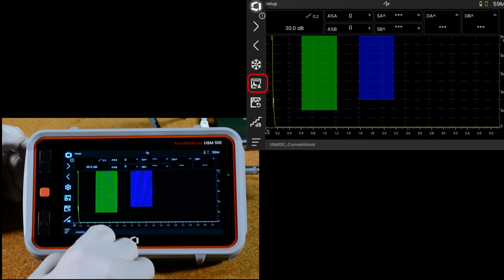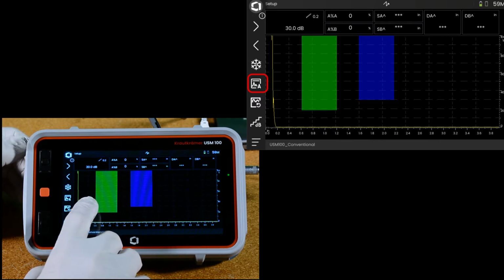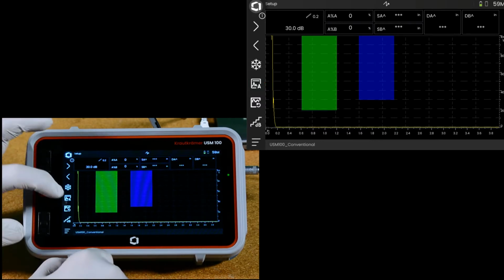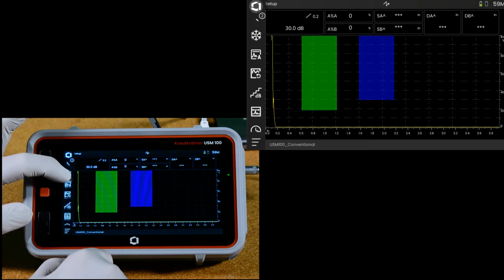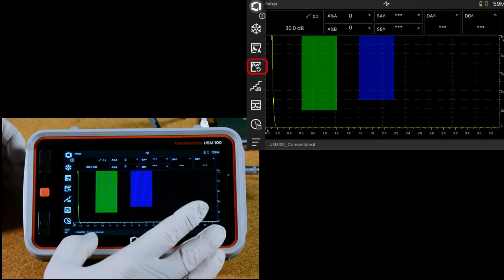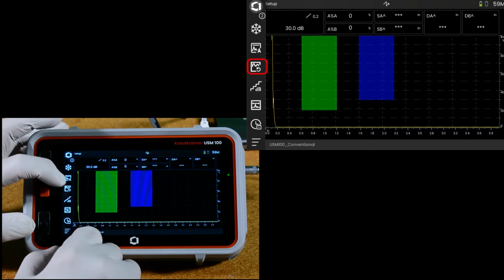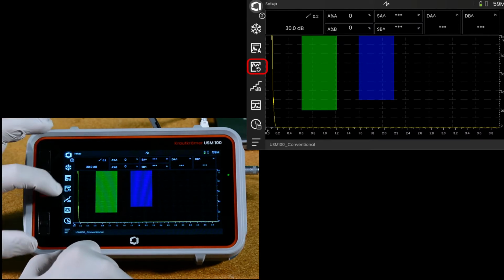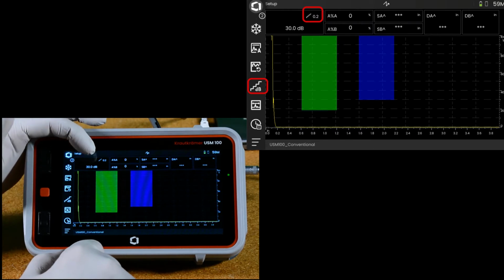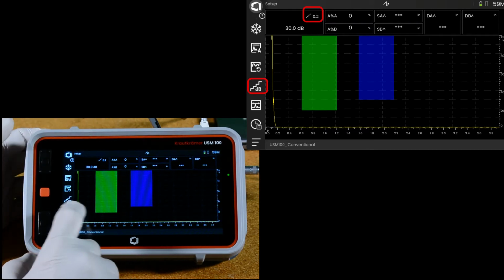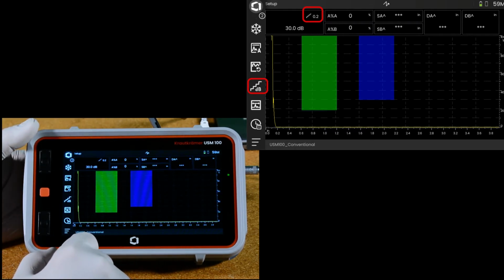That's on one of the menus that we can have a look at a little bit later. Underneath that is envelope clear. So if you happen to have the envelope mode turned on, you can reset the envelope with that button. One right below that is dB step. So you'll notice up here in the gain control, there's a little step icon, and right beside it a number. That is how much your gain will change each time you increment or decrement gain.